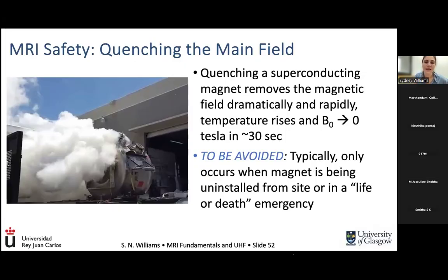And this will essentially open a valve and allow all of the liquid helium to quickly burn off. And then the main magnet will lose its magnetic field strength in around 30 seconds. But you would never do this unless it's a life or death situation, because it will pretty much decommission your magnet. So this could be potentially on the order of a $1 million or pounds or euro type decision.